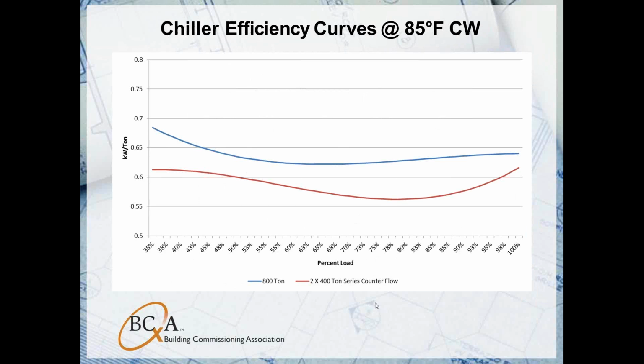So you might ask, why series counterflow? Well, a big reason is efficiency gains. On this efficiency curve, the y-axis is kW per ton, while the x-axis is percent load. Our upper curve here is the efficiency curve at 85-degree condenser water. And you can see that series counterflow is fairly significantly more efficient than the 800-ton chillers themselves.